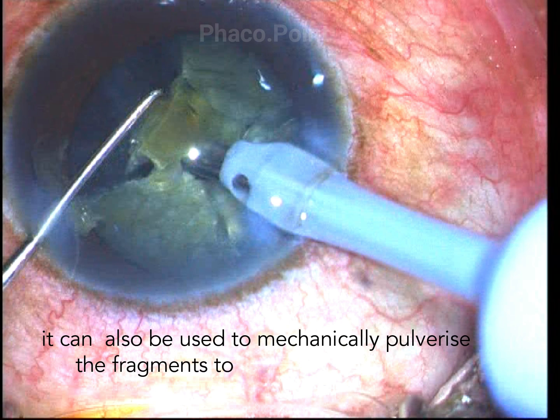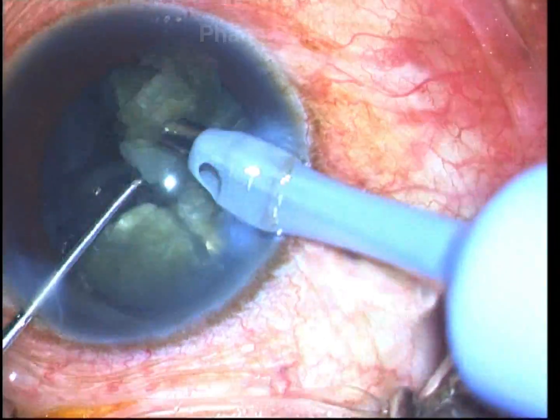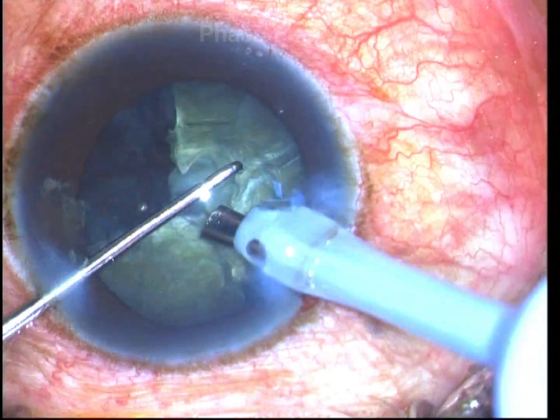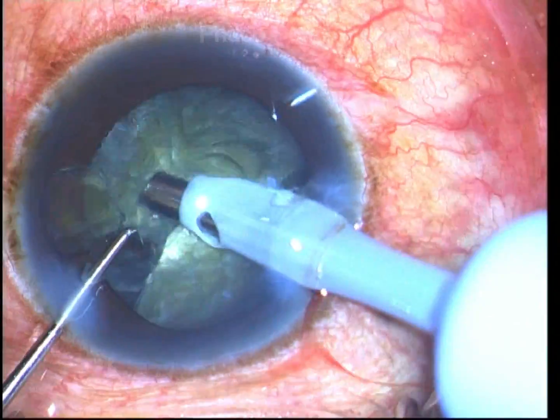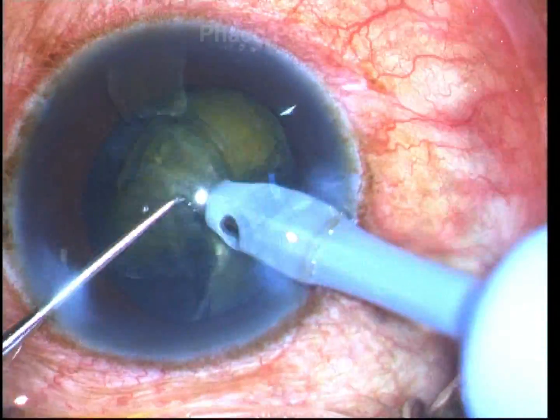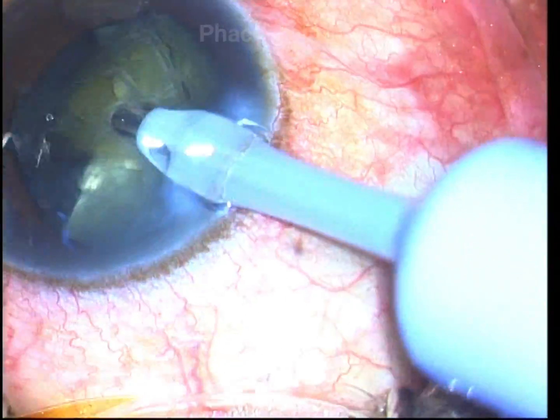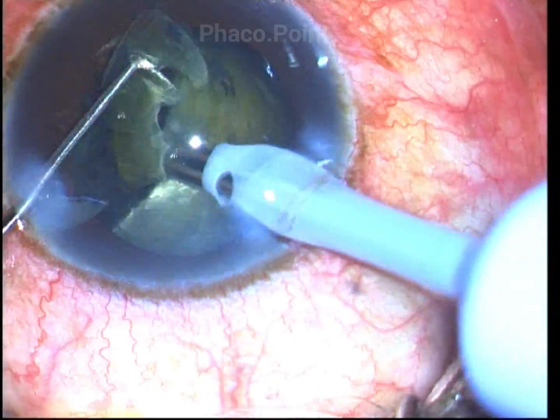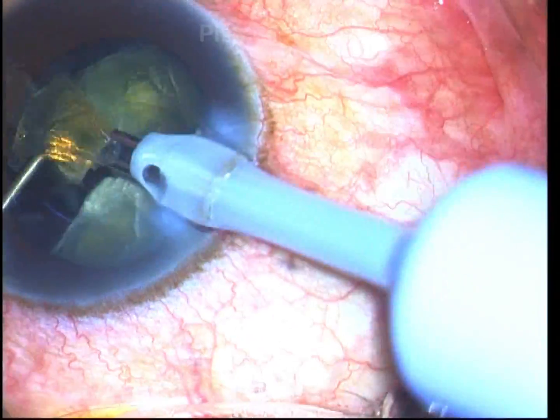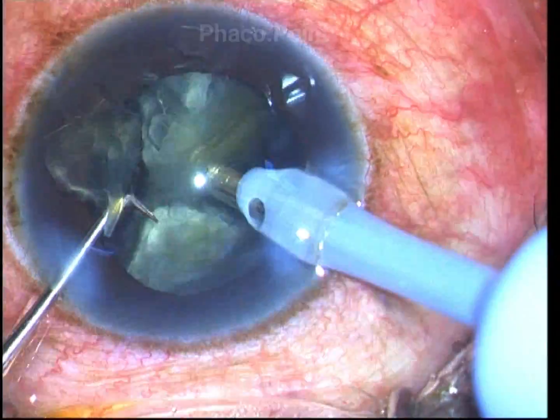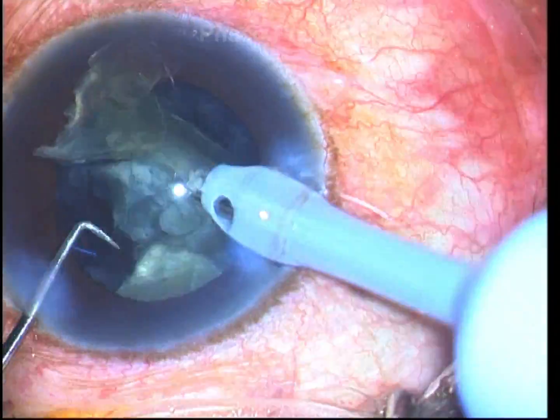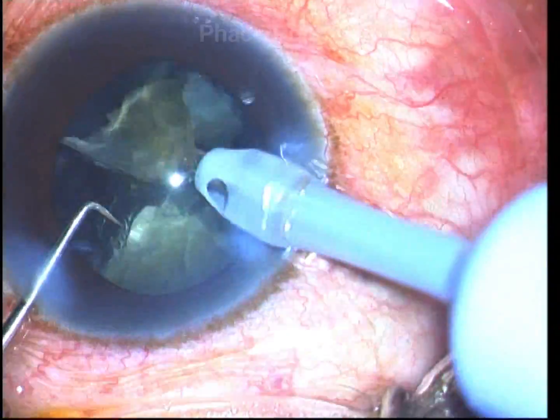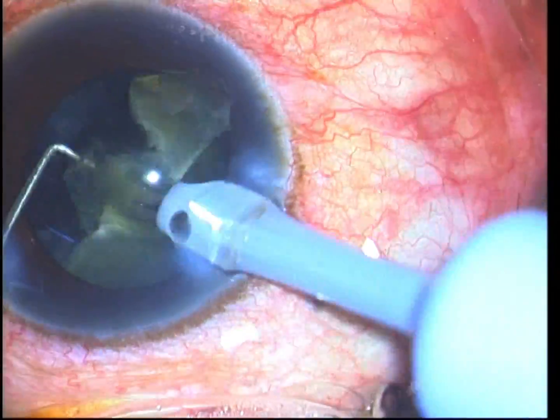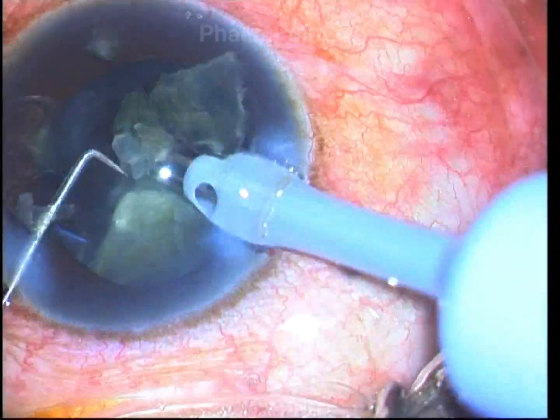I also use the sharp tip chopper to pulverize the nucleus mechanically in order to minimize the phaco energy. But while performing this maneuver, you have to be very careful that you do not contact the phaco tip with the sharp chopper, as this can cause damage to both the tip as well as the chopper. So maybe it is not a good idea to do this. You just use the sharp chopper to manually position the pieces optimally so that occlusion can occur fast and the phacoemulsification can take place with a minimal amount of phaco energy.